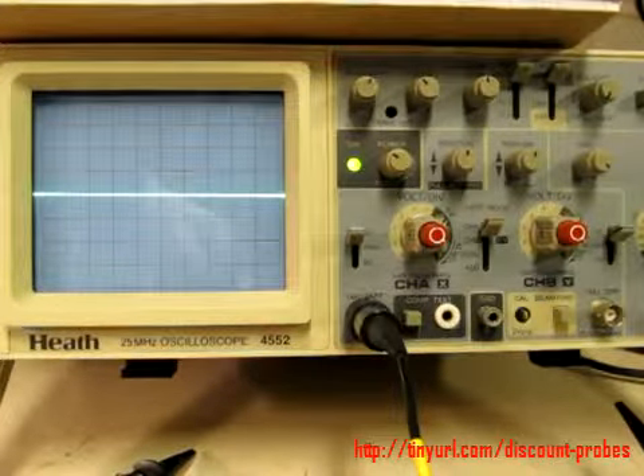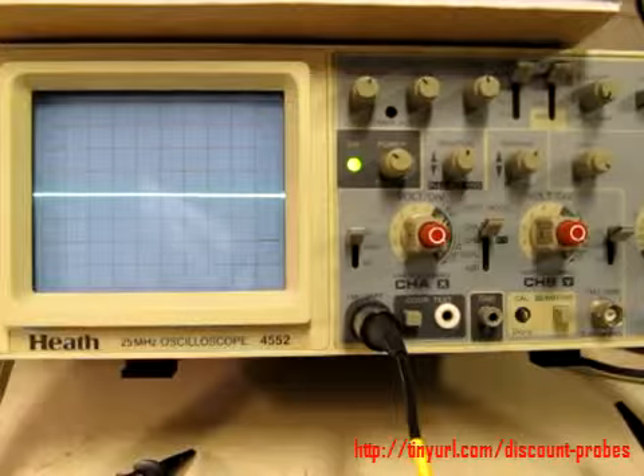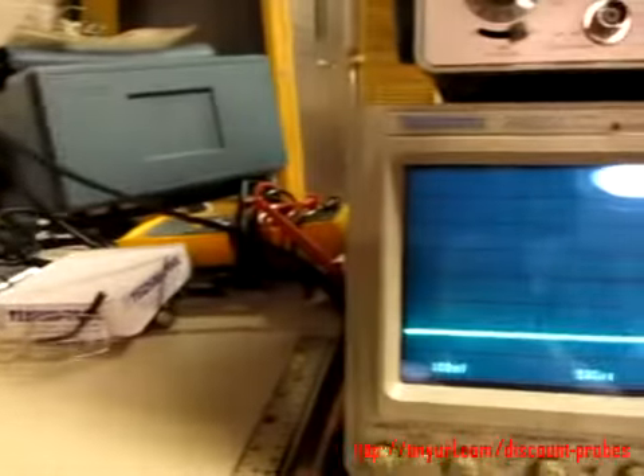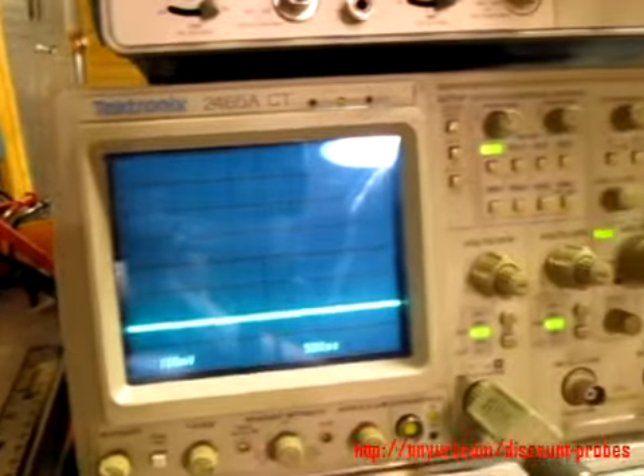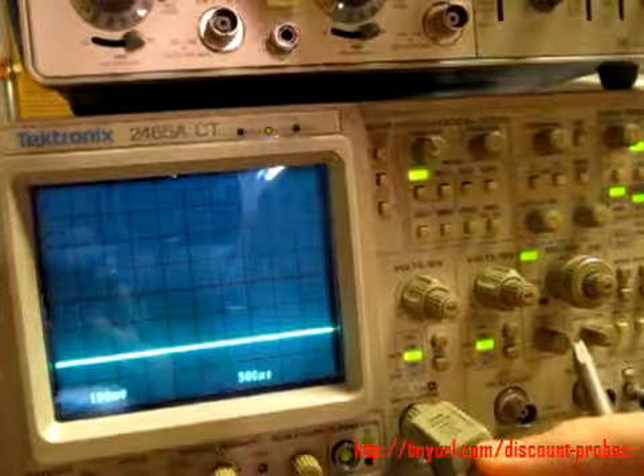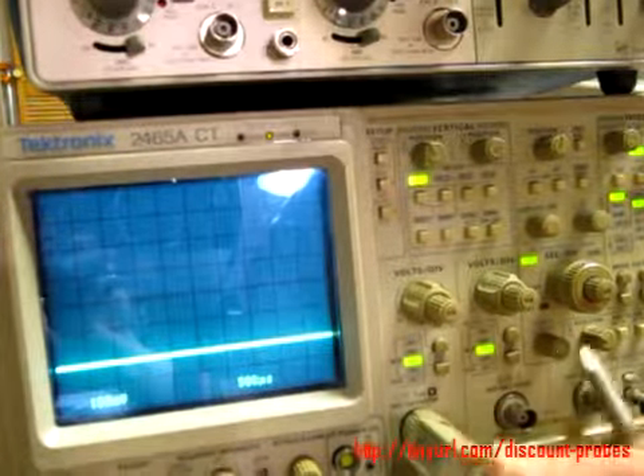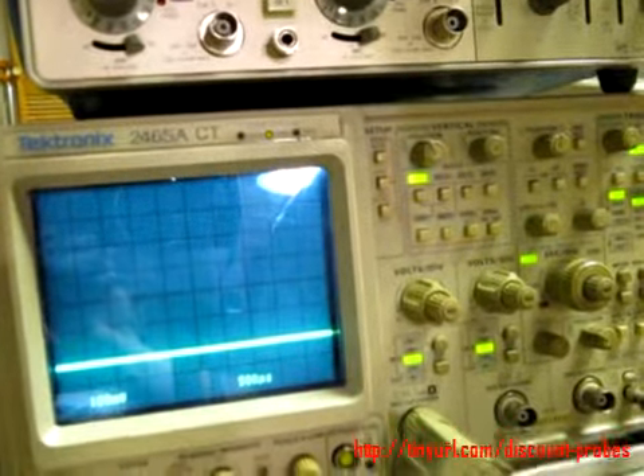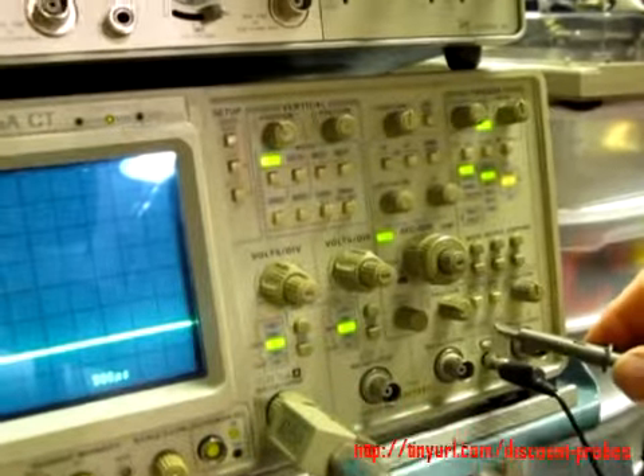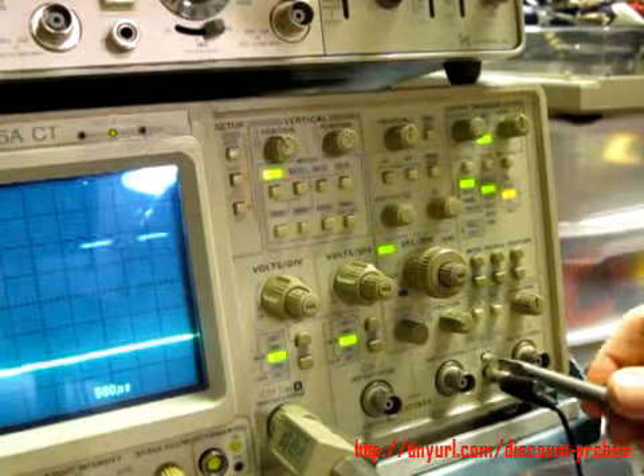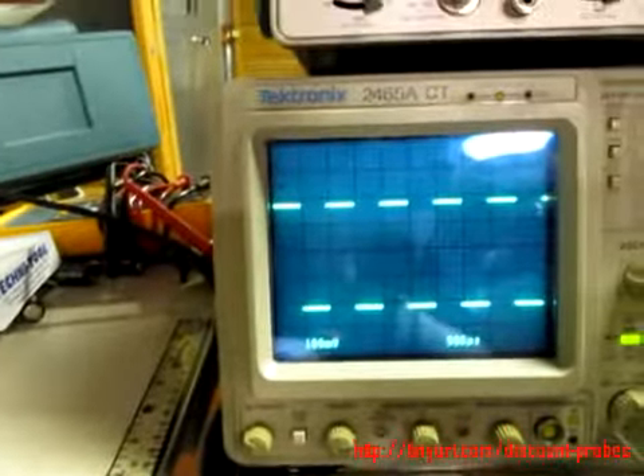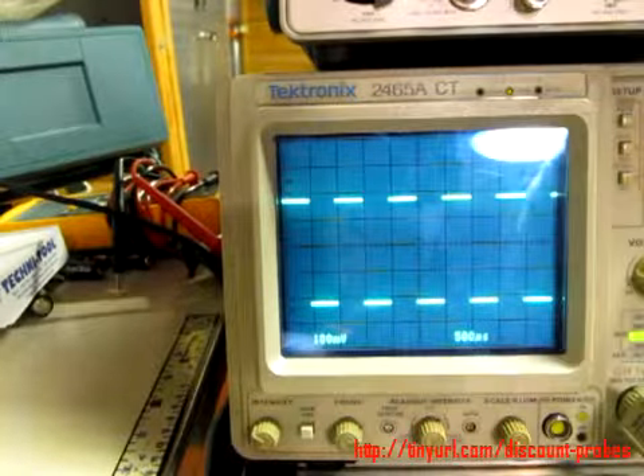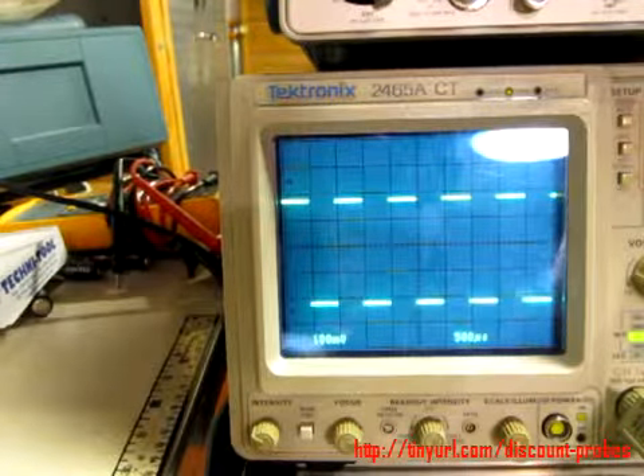And the way to adjust these probes is actually quite simple. Let's look at the example over here on this scope. In this scope here, I've got a P6131 10X probe connected up to channel 1. And on this scope over here is our calibrator signal. Okay, and I've got the ground lead already connected. If we connect the probe to it, we can take a look here at the waveform. And this one is pretty well compensated.